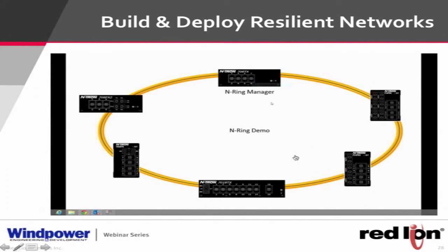With the N-Tron switch line, the only thing you have to do is set the ports the way that they should be, which means plugging them into the right ports, port 1 and port 2, to carry the ring. It's either the first 2 ports or the last 2 ports, and then log into one of the switches and make a change from auto member to master. You don't have to log into every switch. You only have to log into one.